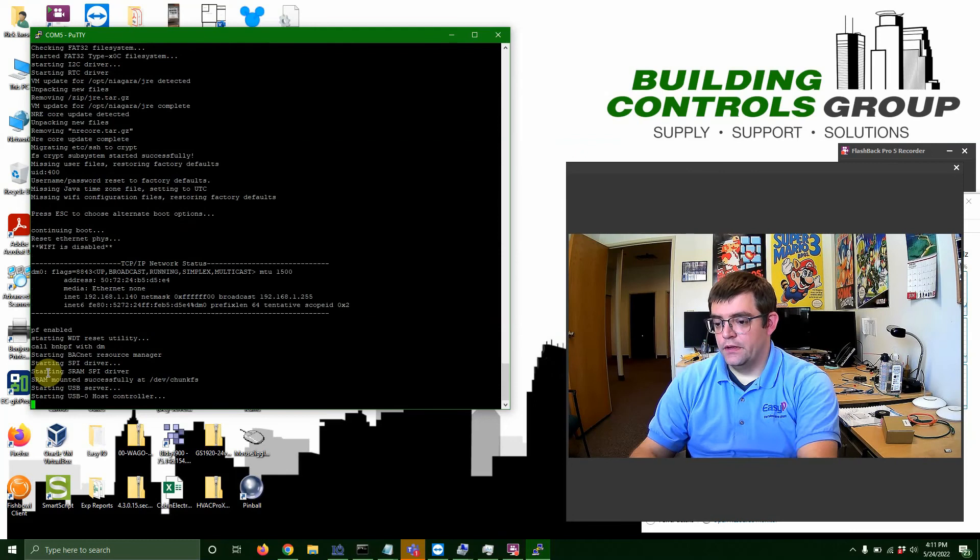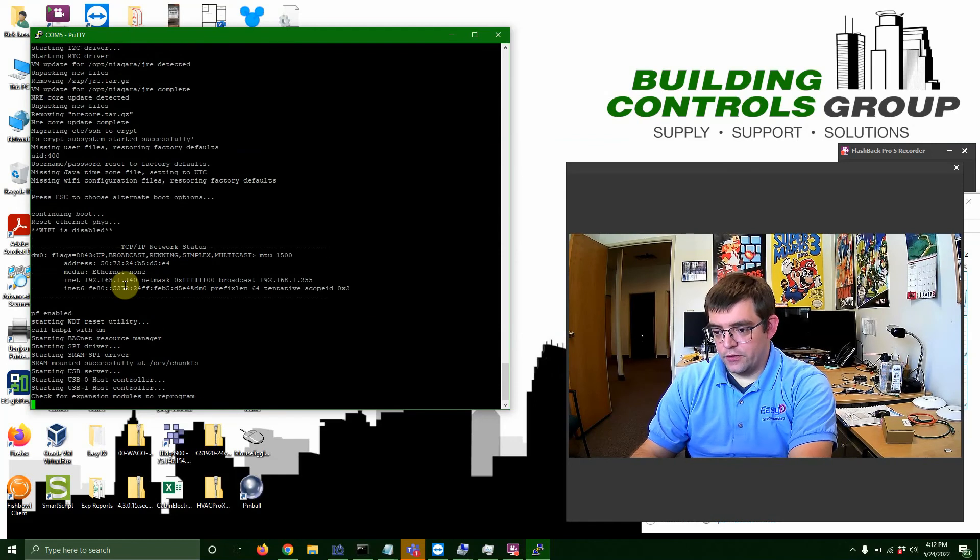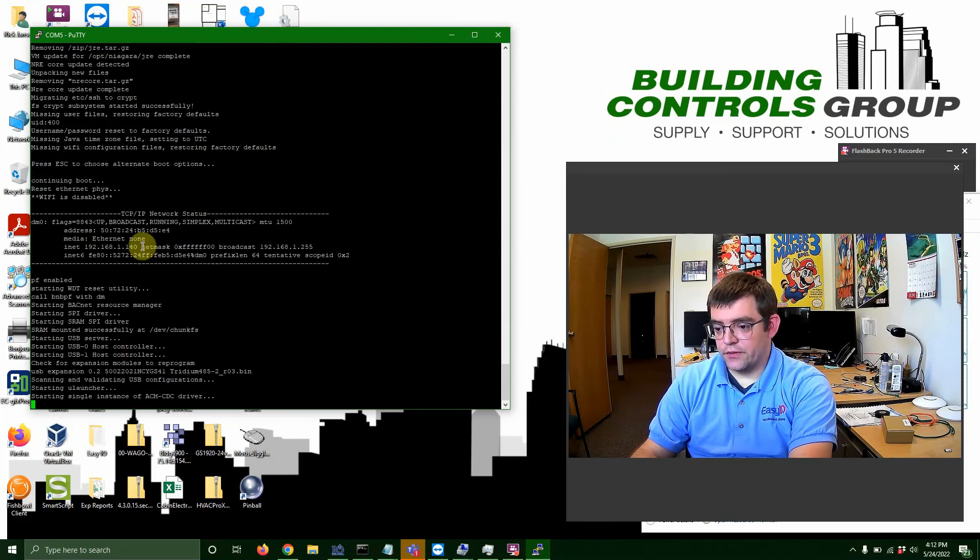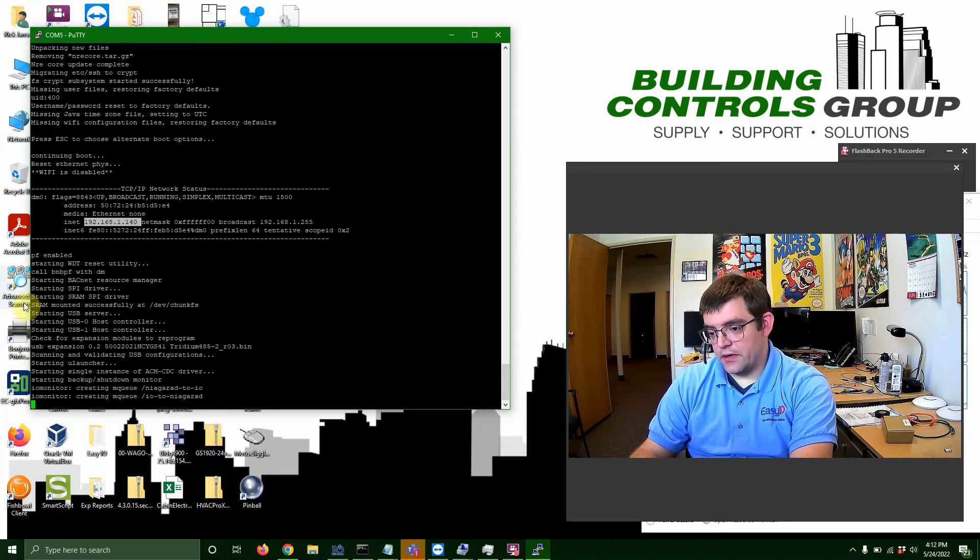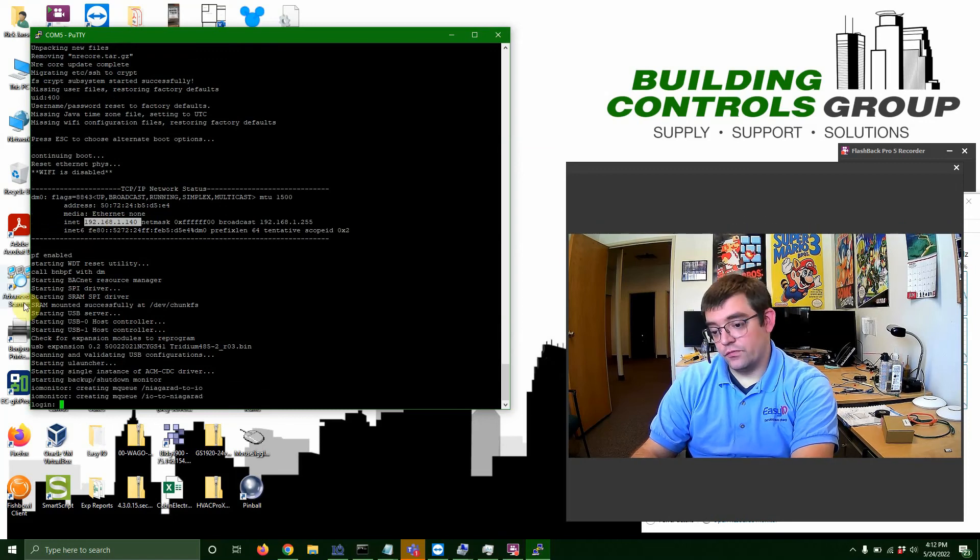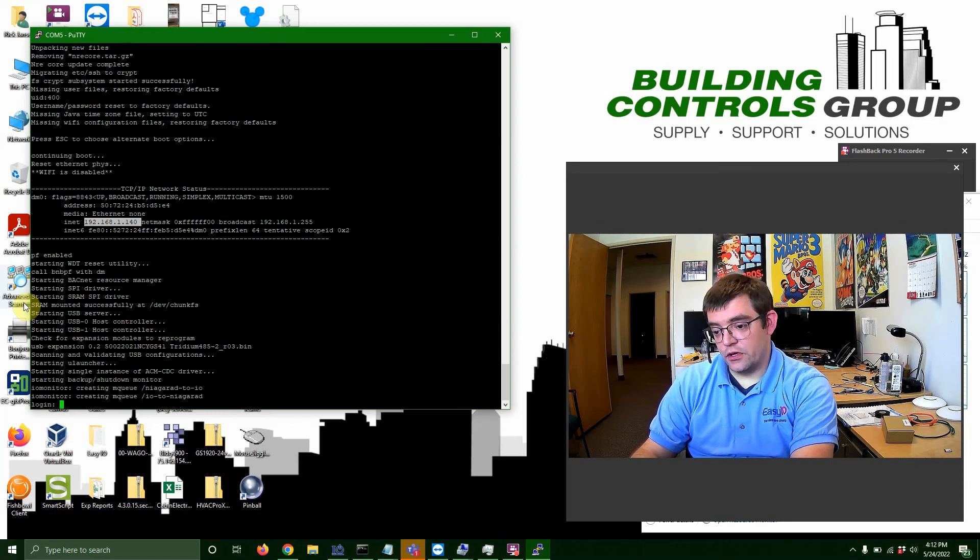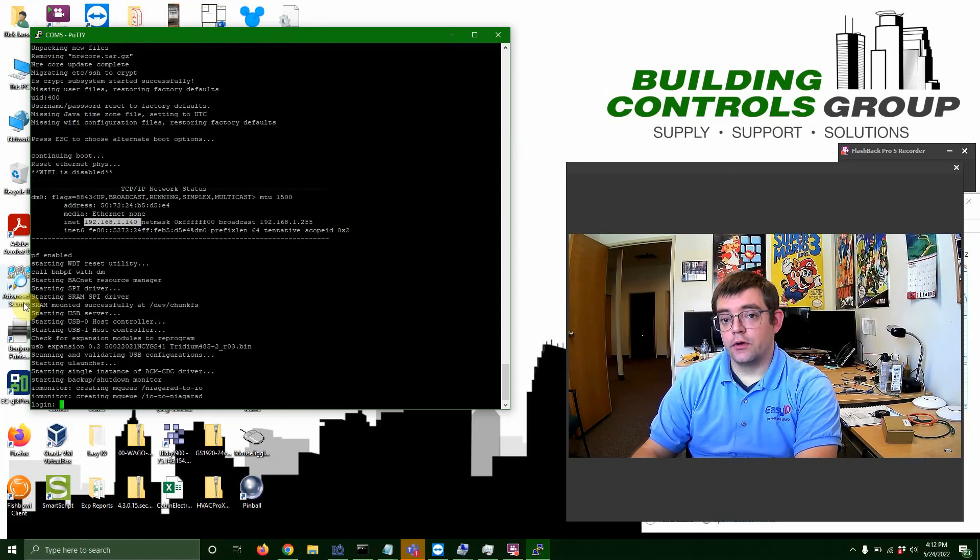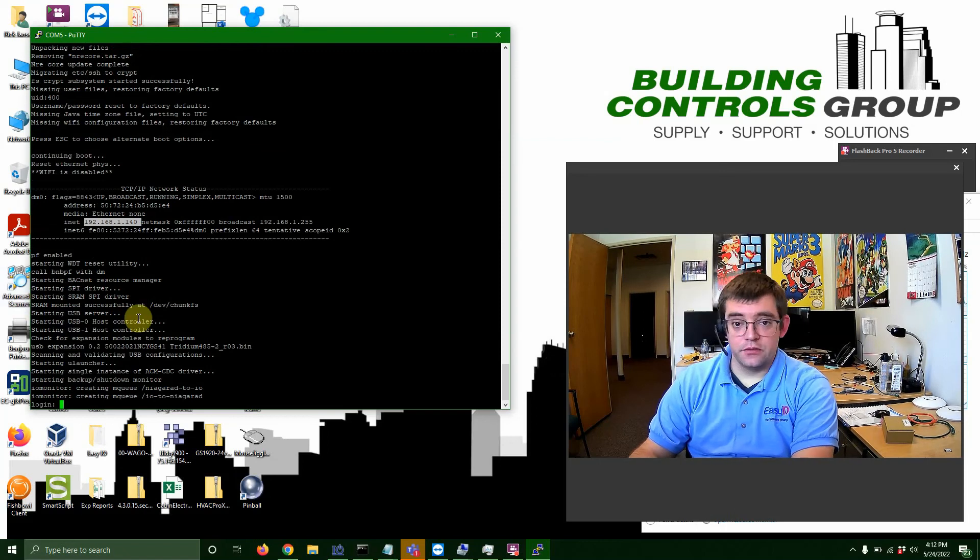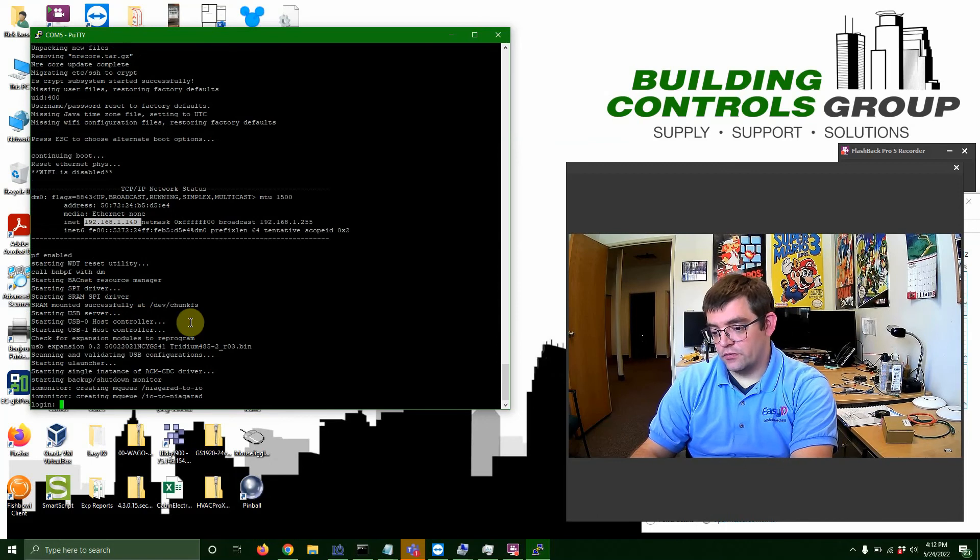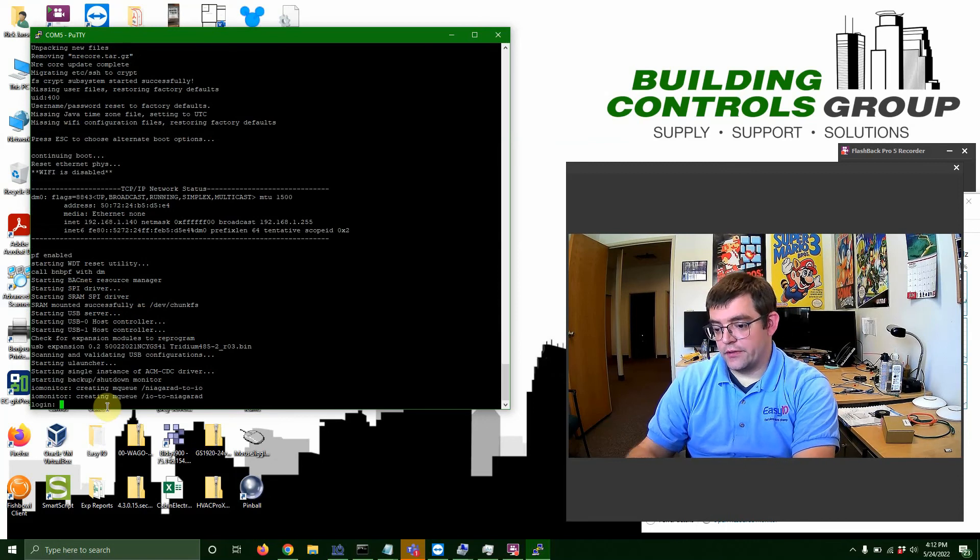So we are basically at the point where it's almost done doing its thing. You can see it has wiped my Jace back to its factory credentials of, you know, 192, 168, that one, that 140 is typically Vykon and some other brands. If it's a Johnson FX 80, it's going to be 149 instead of 140.